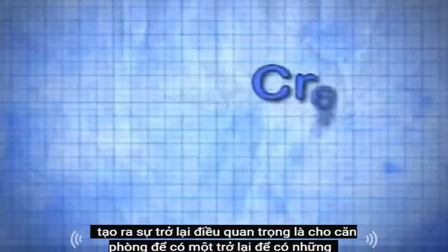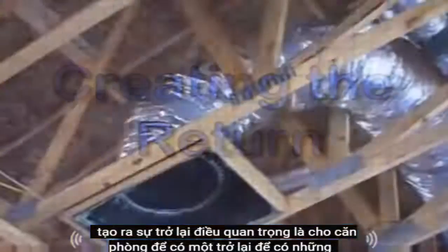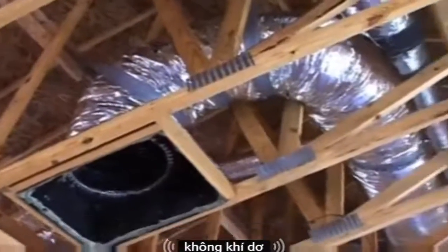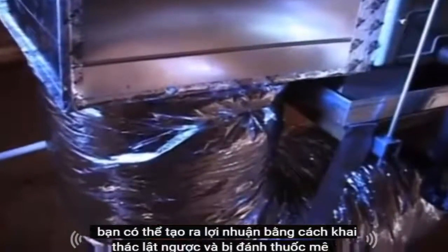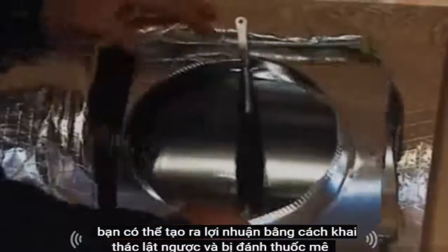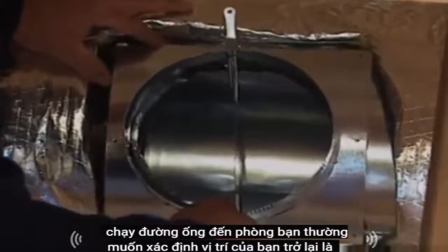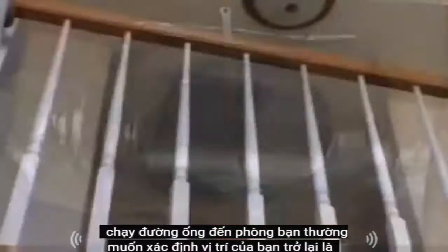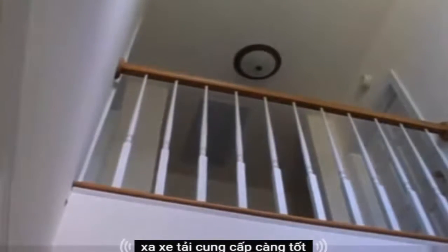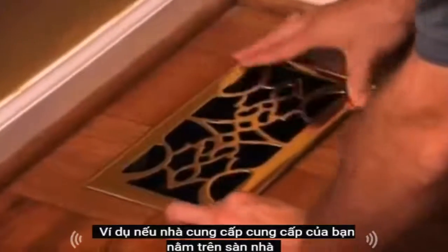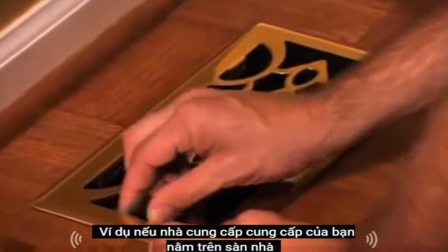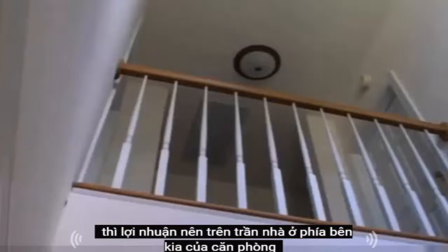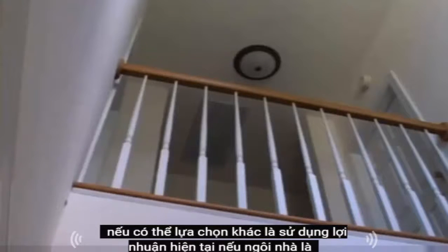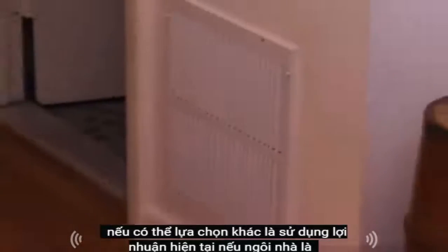Creating the return. It is important for the room to have a return to take the stale air out of the space and return it to the HVAC unit. You can create a return by tapping into a return duct and running ductwork to the room. You'll typically want to locate your return as far away from the supply vents as possible. For instance, if your supply vent is located on the floor, then the return should be on the ceiling on the opposite side of the room, if possible.